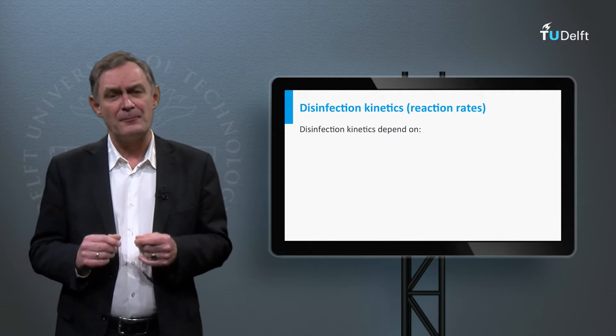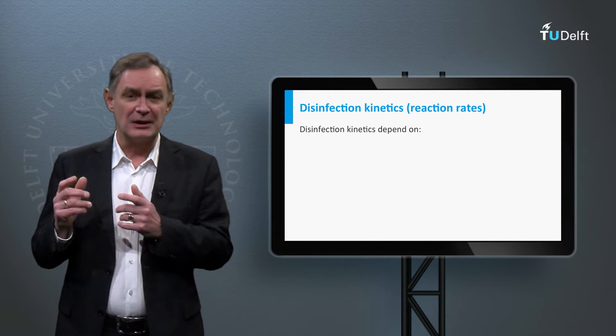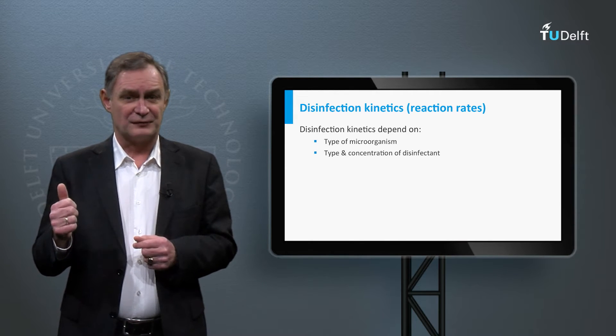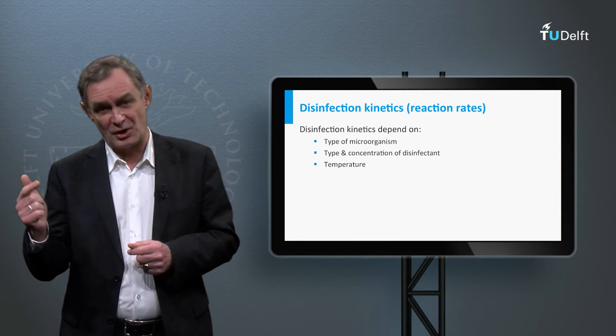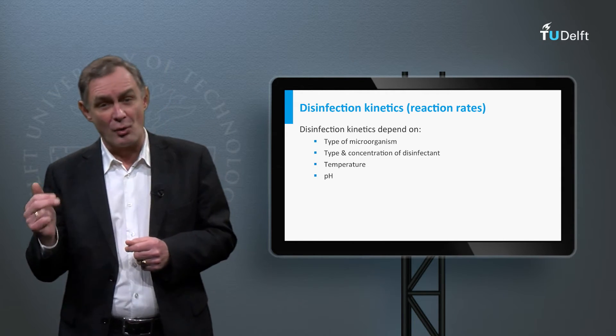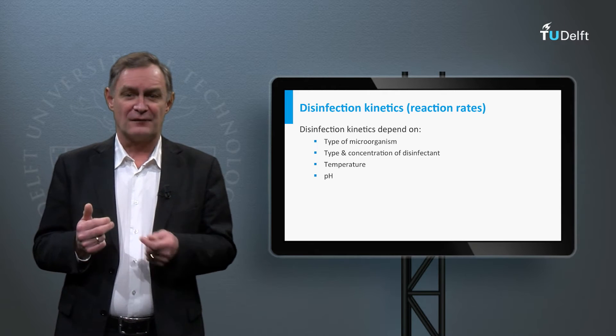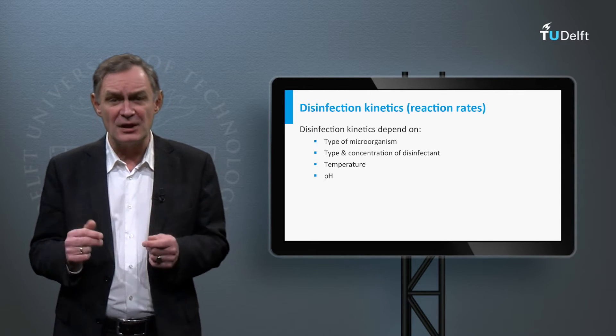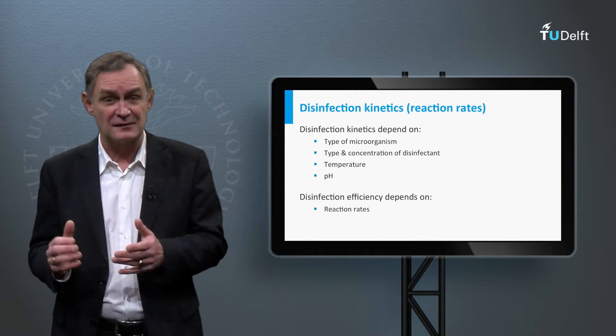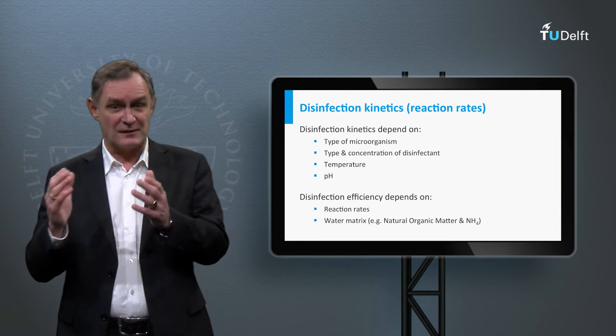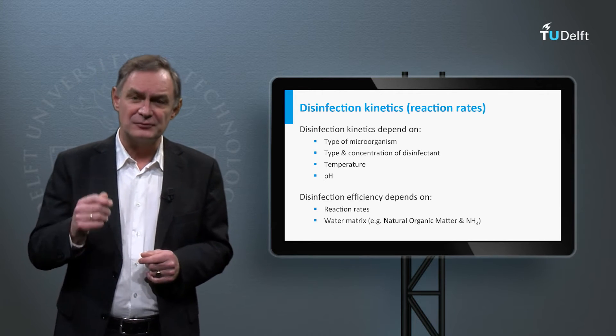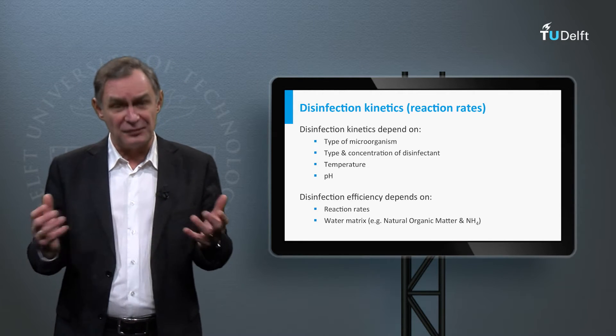Besides the type of microorganism, the kinetics of disinfection also depends on the type and concentration of disinfectant, the temperature – with a lower temperature the disinfectant is less effective – and the pH; the lower the pH, the more effective chlorination is. The efficiency of the disinfection method also depends on the matrix of the water, such as the presence of natural organic matter or ammonium, because these substances also react with the disinfectant.